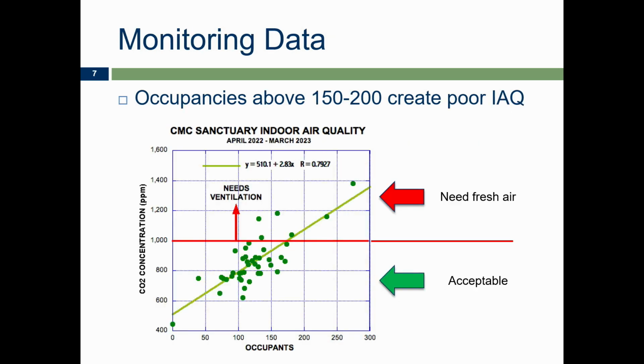This is fascinating—I enjoy working with Professor Bob because he pushes us to do things like regression analysis for indoor air quality. Here we're charting number of occupants against CO2, and the red line shows that at a relatively low number of people, around 150, we're already reaching 1,000 ppm. These aren't exact science, but they're design criteria that create thresholds for how we design systems. At low occupancy we're okay; when we push way up, we're not.